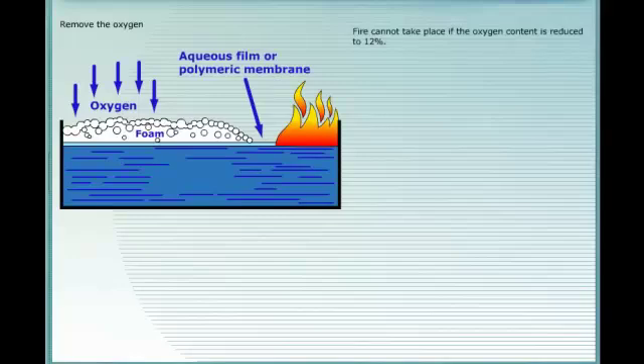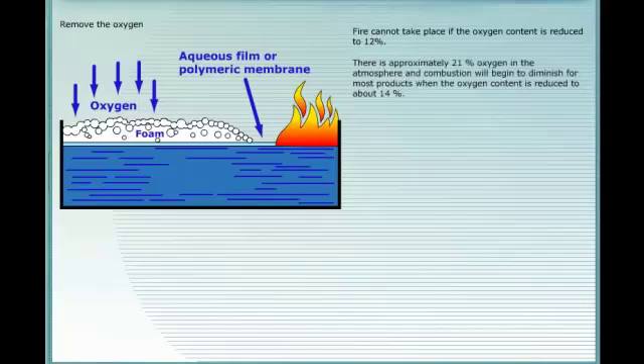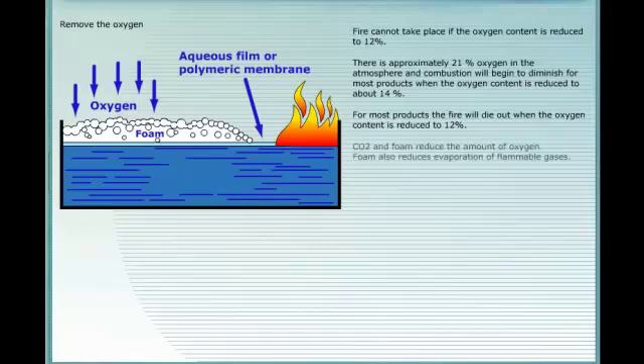Fire cannot take place if the oxygen content is reduced to 12%. There is approximately 21% oxygen in the atmosphere, and combustion will begin to diminish for most products when the oxygen content is reduced to about 14%. For most products, the fire will die out when the oxygen content is reduced to 12%. CO2 and foam reduce the amount of oxygen.